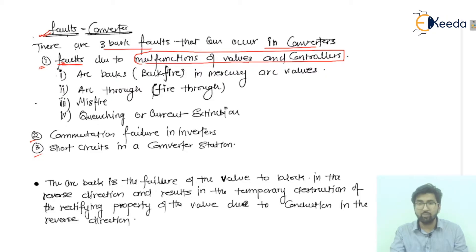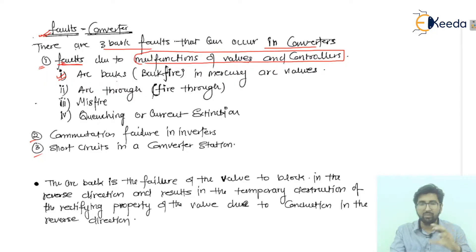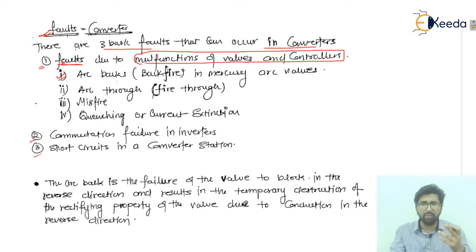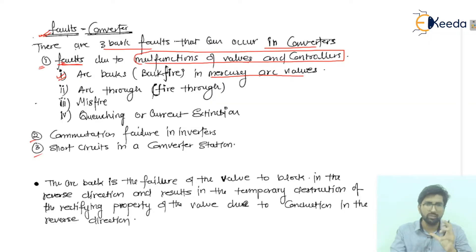The first cause is arc backs. Whenever in reverse bias conditions, arc back is found in the mercury arc valves — that is, in reverse direction operation. Arc back is generally called backfire, and it generally happens in mercury arc valves. But as we advance to modern technology and replace with thyristor valves, arc back does not occur in thyristor valves.